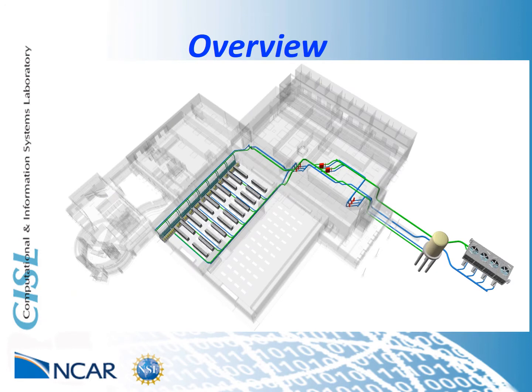This slide is a quick overview of the footprint of the NWSC with the cooling tower, water tank, and cooling distribution system layout. The water tank is a 60-foot tall tank containing 135,000 gallons of water with a nitrogen blanket atop the water line. The NWSC design has 2 modules, A and B.